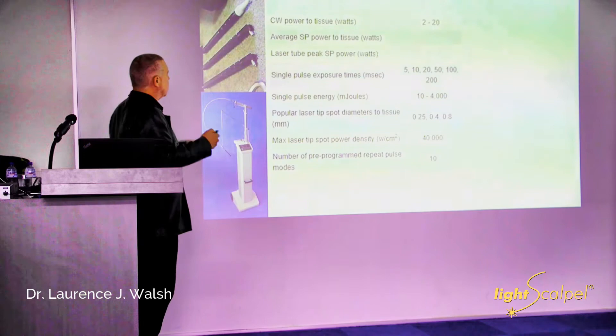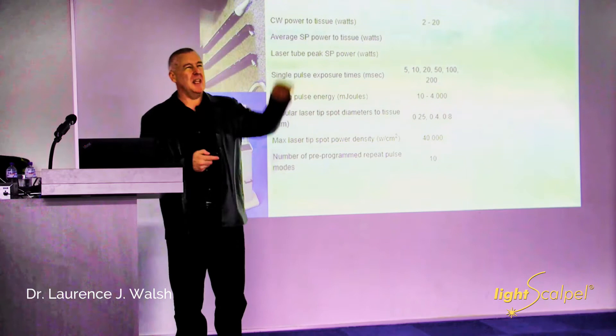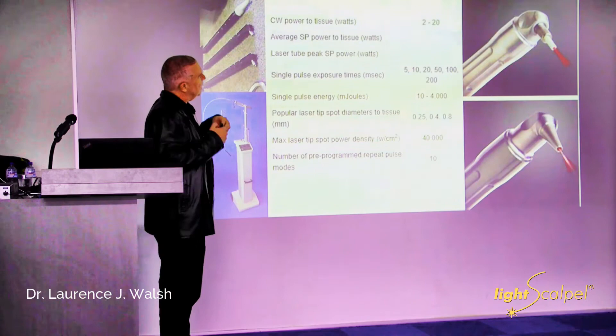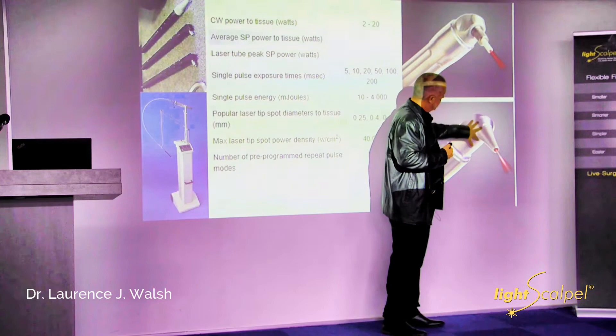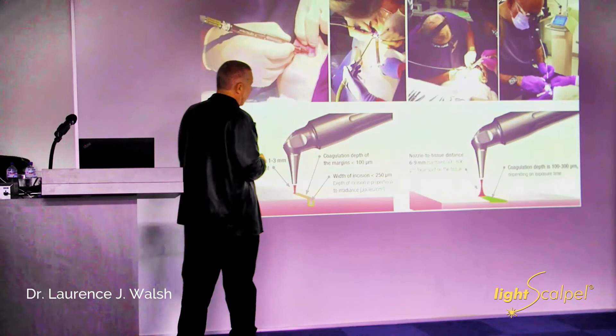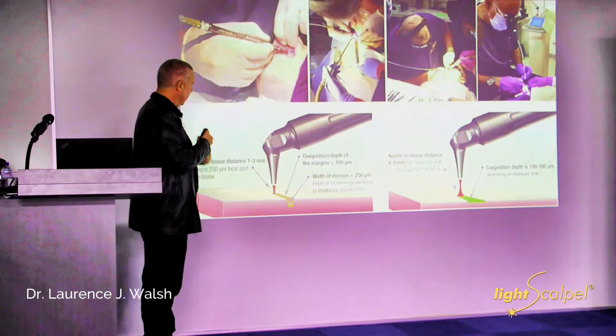This laser comes in a range of different powers. While 20 watts might seem like a lot, many surgical procedures in dentistry don't use the maximum power — they use modes where the instantaneous power is greater. You deliver it through different sorts of tips: some have little disposable ends made out of aluminous ceramic, and some are basically tipless handpieces which focus down to a spot. I like to think of these as the knife and the trench — do you want to cut a neat little slice, or a trough? By changing the distance from the tissue, you can alter the interaction very easily.